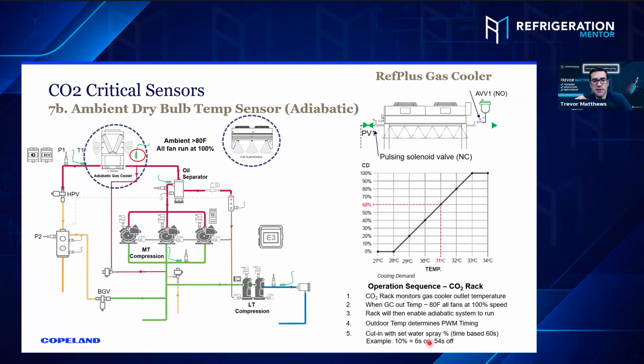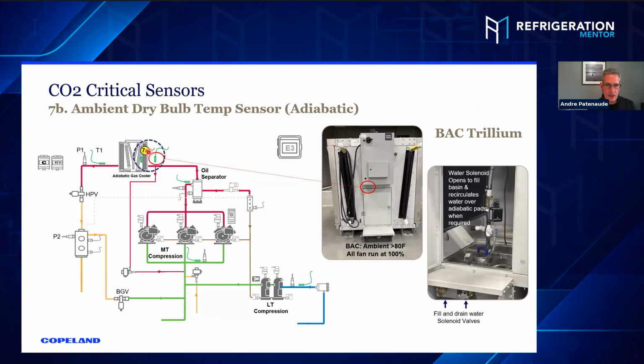Yeah. And that's important to understand, because these sensors are not doing just one thing. It's not just the ambient air. Like, oh, we look at the ambient air. It's actually doing control of the system. I want to talk just about the pre-cool sensor, just to make sure that I'm clear. The pre-cool sensor is compared to the drop leg sensor, and that is controlling the subcooling while it's still in subcritical mode. Is that correct? The pre-cool sensor, 7A. Yep. And T1. Against T1, so that measures a TD across that coil for fan speed. For fan speed. Okay. The subcooling is managed by T1 and P1. P1 in the high pressure. High pressure. Yeah, sorry. So it's the fan speed control, 7A, T1.